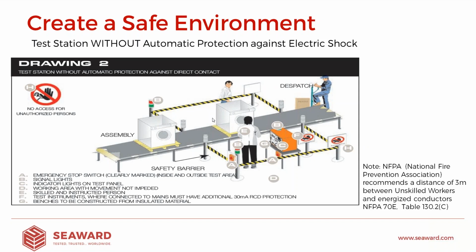The test area is very much part of that line. So we have to consider both the area around the operator and the area in which people could be working or walking. So in this case, we've created a full squared-off situation, which is well away from the item under test. So the dispatch clerk and the guy wandering around the factory physically cannot come into contact with the product. They can't reach over. The barriers are a sufficient distance to enable that separation to exist.